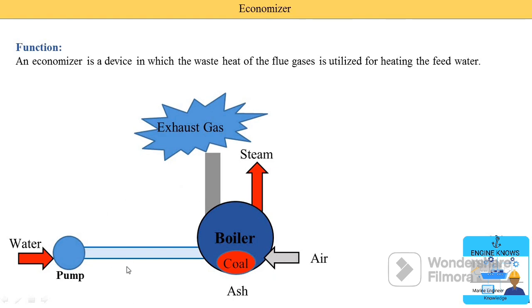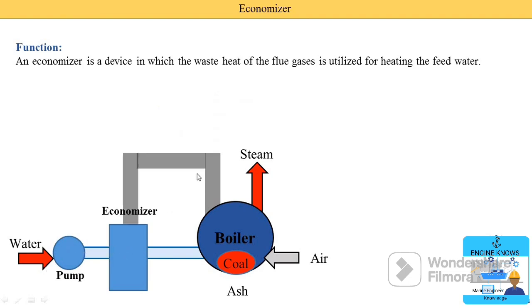If we want to heat the water, we install an economizer. If we need to heat the air, we put an air preheater. If we want to heat the steam, we put a superheater. All three components use the exhaust gases for heating. The water from the pump comes into the economizer, and the exhaust gas is also supplied to the economizer, heating the water. Then exhaust gases from the economizer go to the air preheater, then to the chimney, and then to the atmosphere.